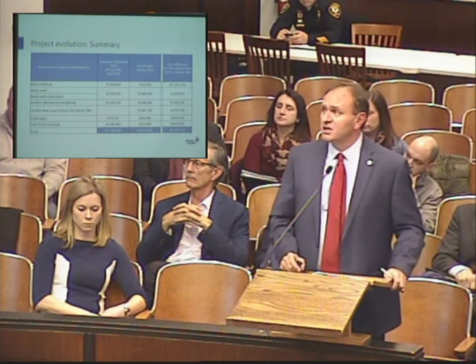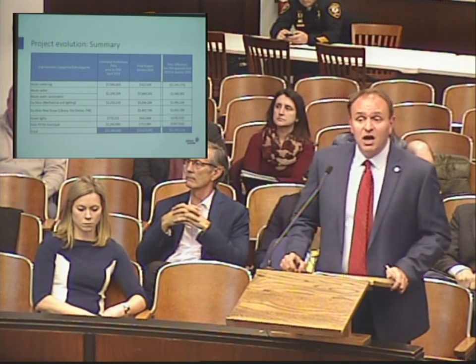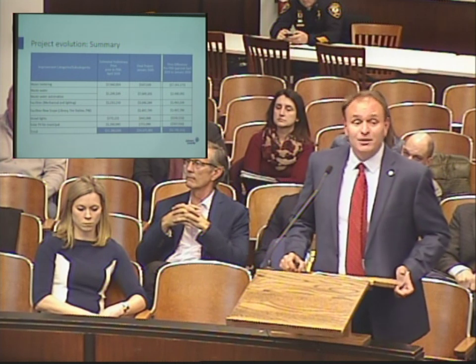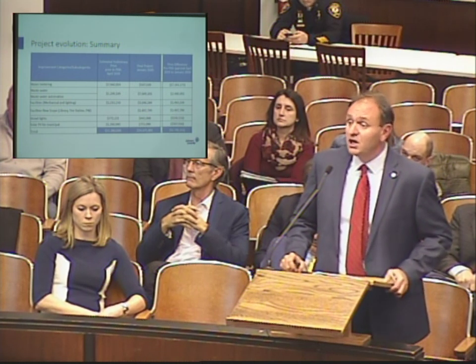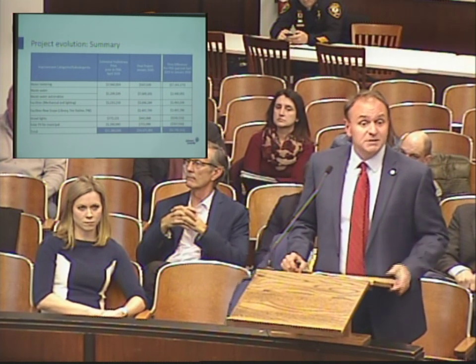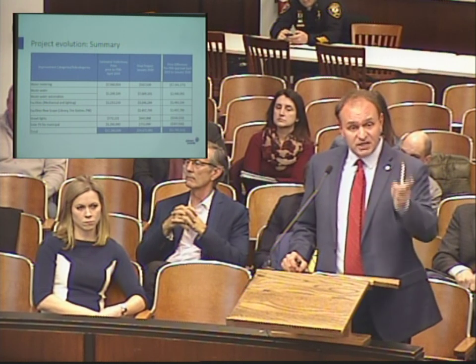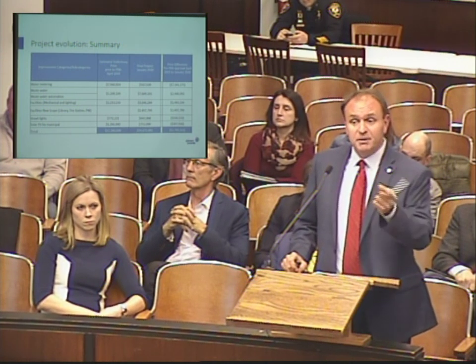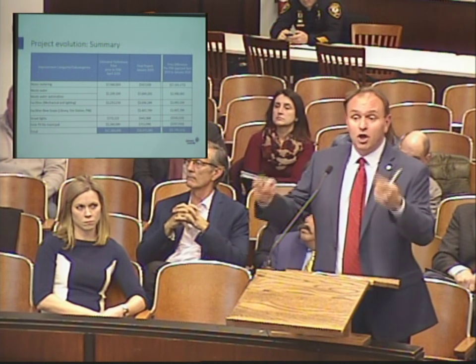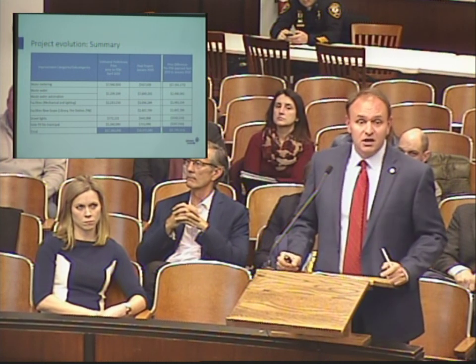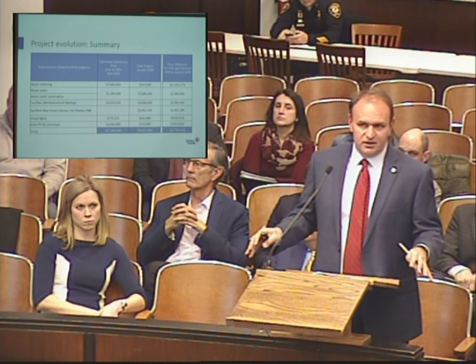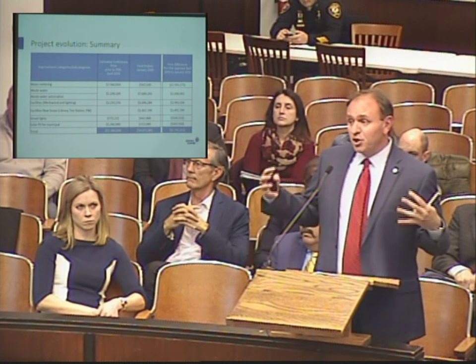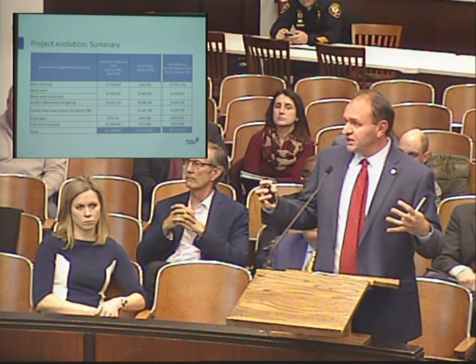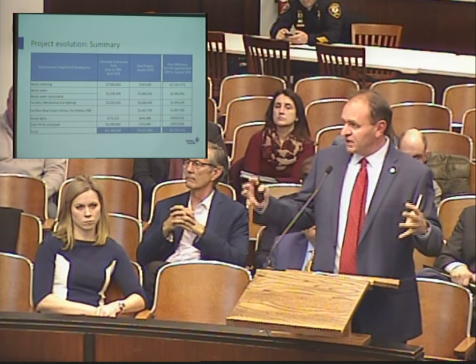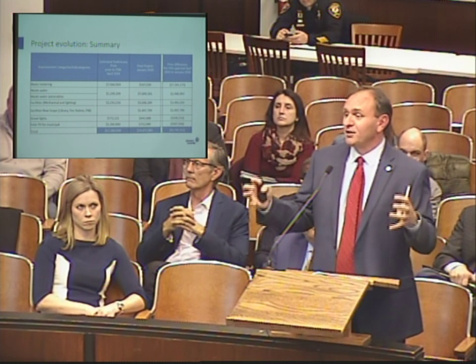To give you an example, the chillers at the fire station are not that old. They are old, but not that old. Why we are recommending replacing them is not because of the chiller itself, but because of the piping and water treatment that goes into the chiller, which was not addressed last time it was done, and the chillers are failing. So this project is not only about energy savings, it's really about addressing your capital needs the way they should be addressed.